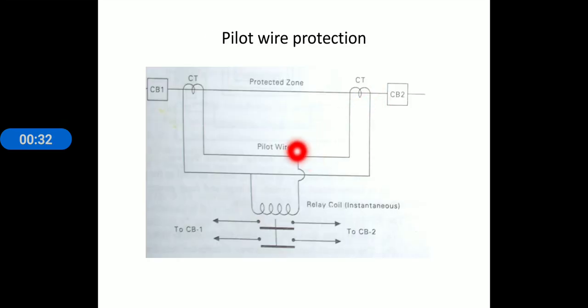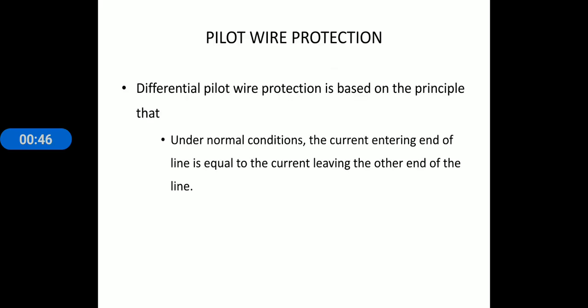protection. Each end of the line is connected with a current transformer. The secondary of each current transformer is connected in series with the other by using wires, and those wires are the pilot wires. Coming to the principle of pilot wire protection, under normal conditions the current entering the line is equal to the current leaving the line.